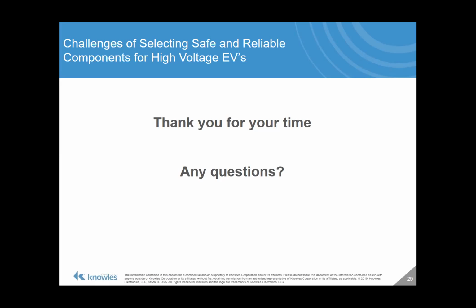Thanks. Okay, sure. So the first question I see up there is, can we explain what we mean by dielectric withstand voltage? I apologize for this. When you're in the industry for so long, you use the terms that you're used to, and you forget that they're maybe not commonly known to everybody. So dielectric withstand voltage is the test voltage, also known as a voltage proof or a withstand test or a flash test. So it's where you test a component or a circuit at a voltage considerably in excess of the rating, and you're doing it to weed out early stage failures.